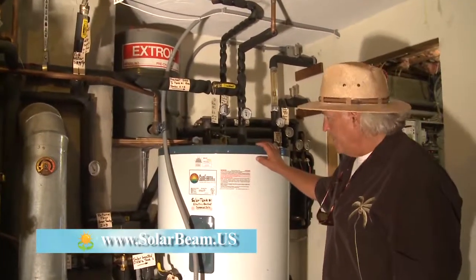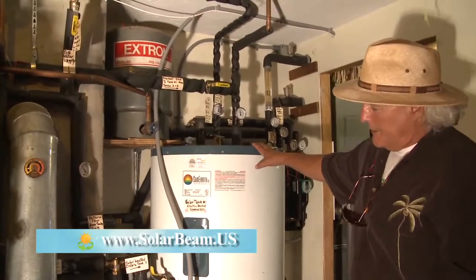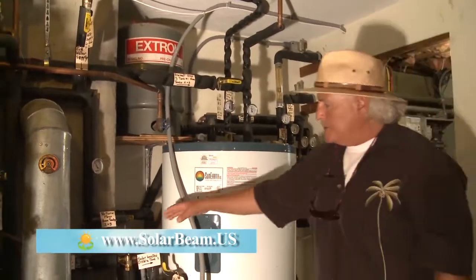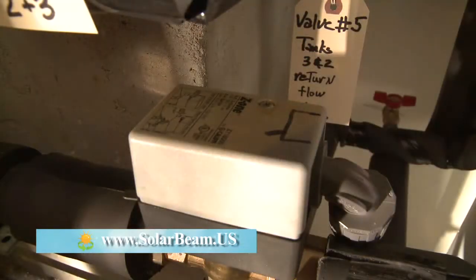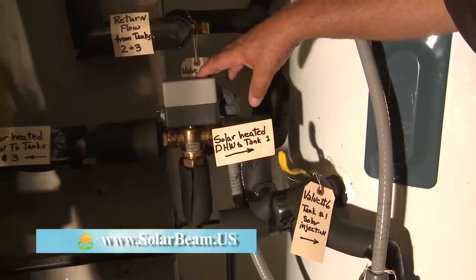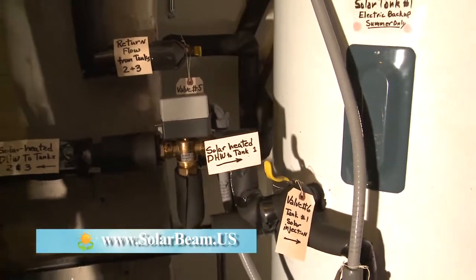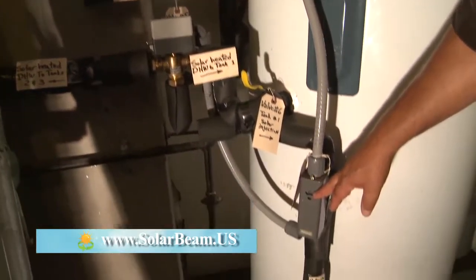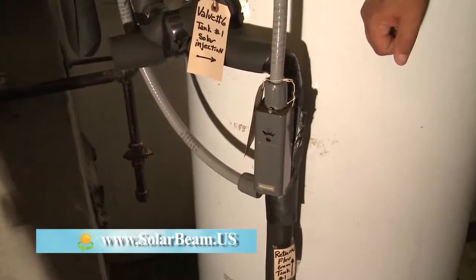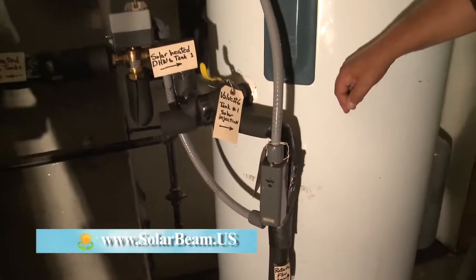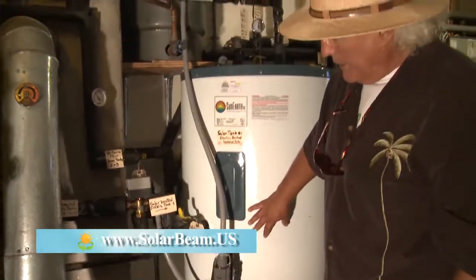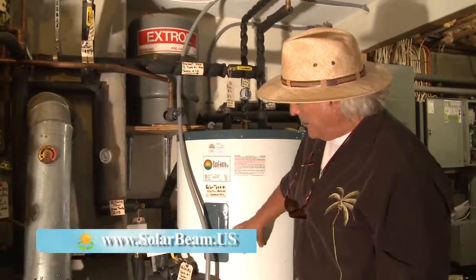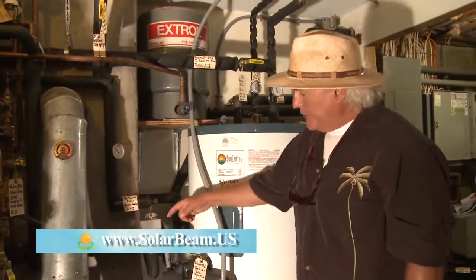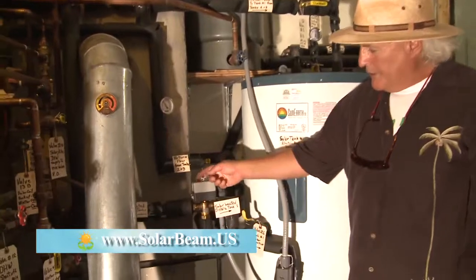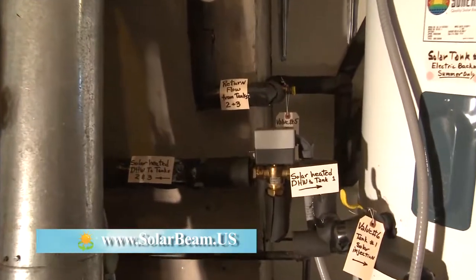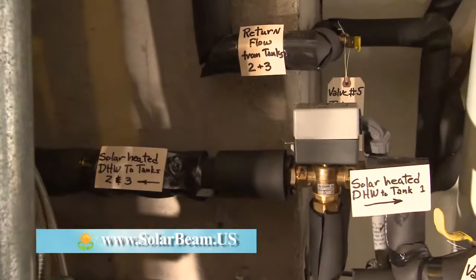This is the primary tank, and the hot water is diverted after it goes to the heat exchanger over here to what is known as a 3-way valve. This is a motorized 3-way valve. The 3-way valve checks the temperature of the water through an aquastat, which is right here, and when the temperature of this tank is below a certain set temperature, it sends all the hot water to heat this tank. Once this tank is satisfied, and I think right now I have it set at 130 degrees, the 3-way valve is activated, the lever will turn, and the rest of the hot water is now diverted to the other 2 tanks, which are about 15 feet away.